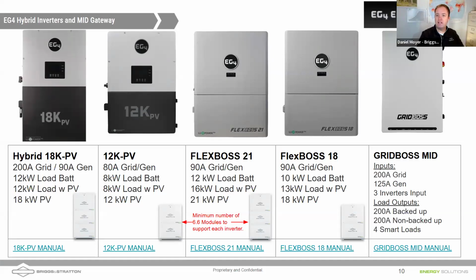Grid Boss on the far right-hand side, 200 amps in, 200 amps right back out. It has the 125 amp generator input. Smart load outputs, we're going to get more into that here in a second.